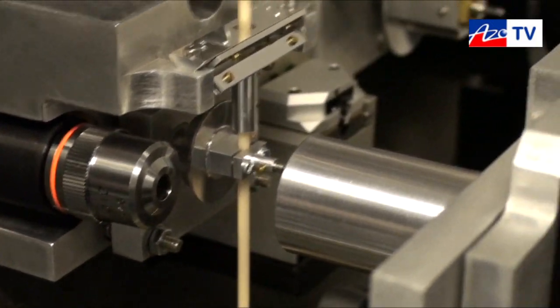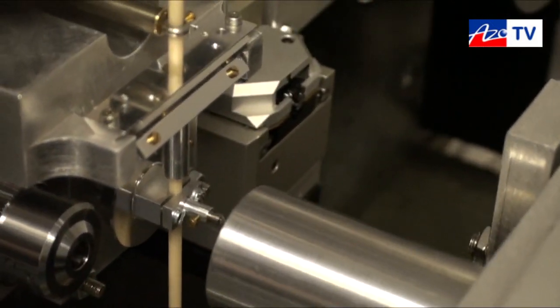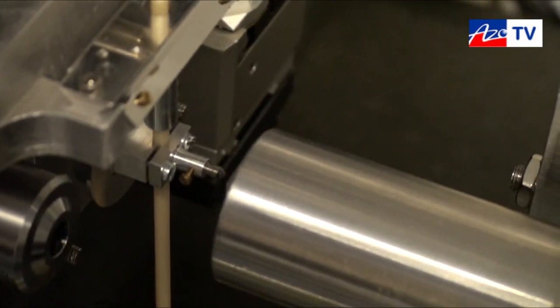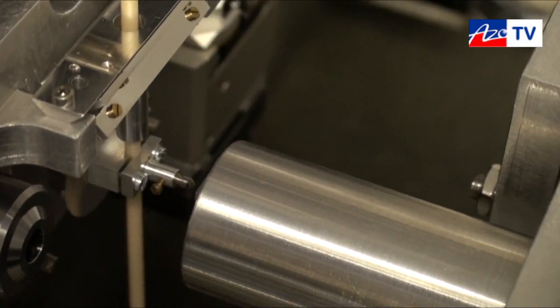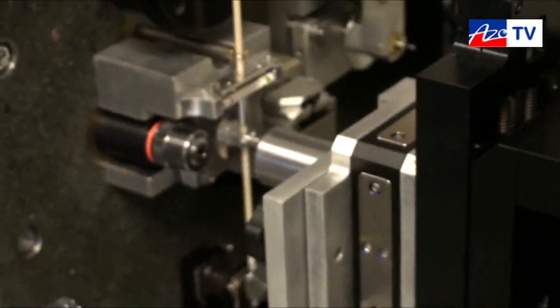So then just next to that is the nano loading head, so the load range on that is from 10 micronewton up to 500 millinewton. So that's a very nice wide range on one loading head.